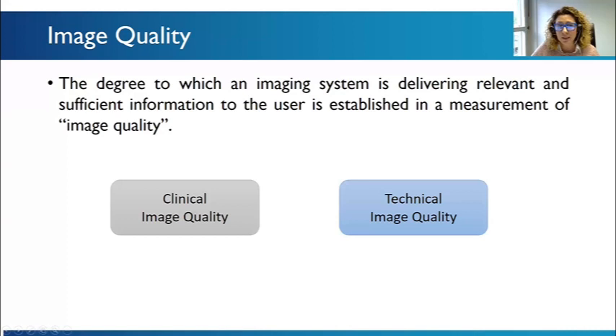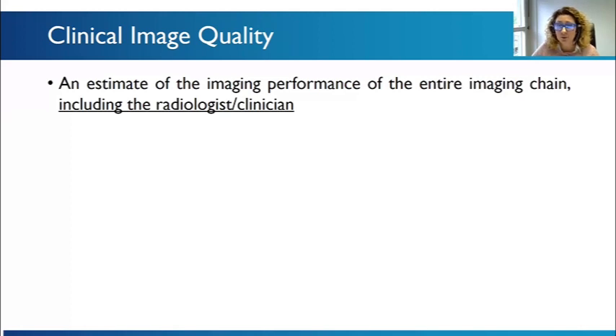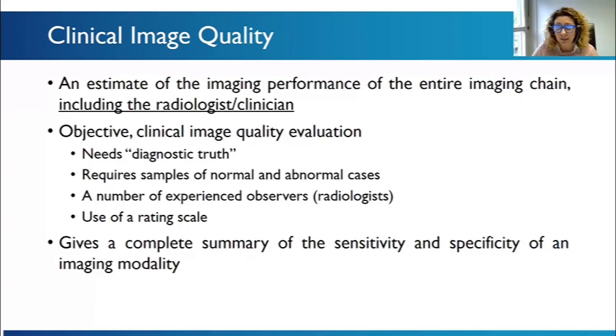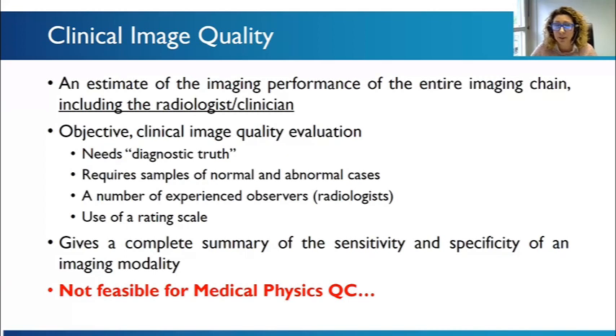We can define image quality in two flavors: clinical image quality, which is actually the goal of setting up good equipment, and technical image quality on the other side, which is what we can estimate as medical physicists. Clinical image quality is an estimate of the imaging performance for the entire imaging chain, where this entire imaging chain includes the radiologist. So it's really what the radiologist says. What we need is an objective clinical image quality evaluation, so we need to know the diagnostic truth. We need samples of normal and abnormal cases, a number of experienced observers, and we need to set up a rating scale. This, in principle, gives a summary of sensitivity and specificity of an imaging modality, but definitely that's not feasible for medical physicists' quality control.